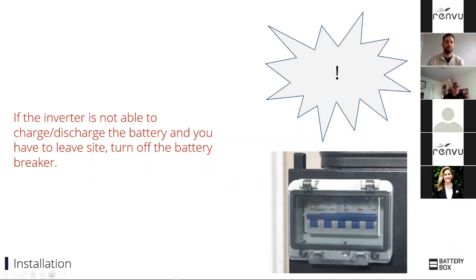What we want to avoid is a lengthy service case. The only time we see problems is if an installer is at site with an inverter that hasn't been commissioned, but has a battery already commissioned and communicating with it. So you have a situation where the battery is powering the inverter, and the inverter keeps using up the battery power until it gets really low and the battery turns itself off.